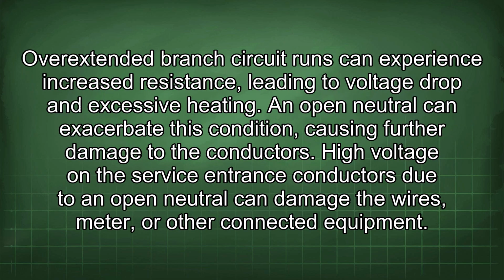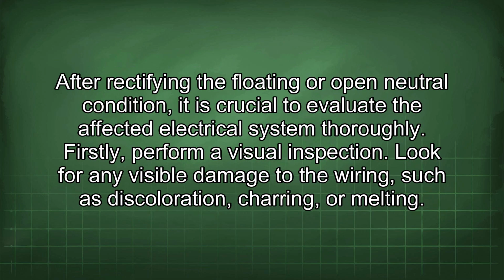Overextended branch circuit runs can experience increased resistance, leading to voltage drop and excessive heating. An open neutral can exacerbate this condition, causing further damage to the conductors. High voltage on the service entrance conductors due to an open neutral can damage the wires, meter, or other connected equipment. After rectifying the floating or open neutral condition, it is crucial to evaluate the affected electrical system thoroughly.